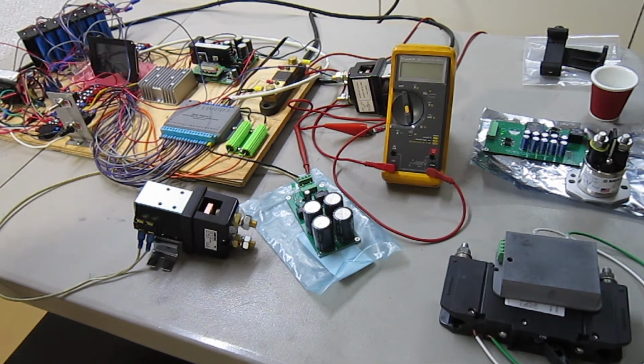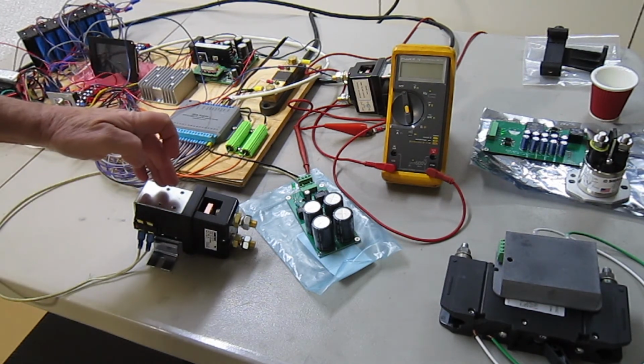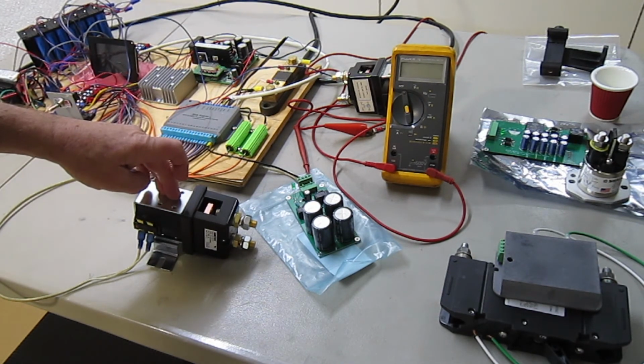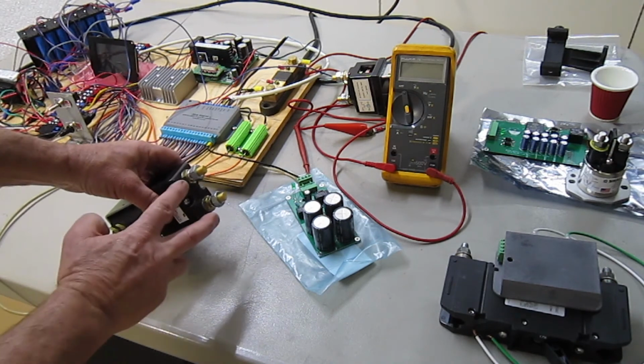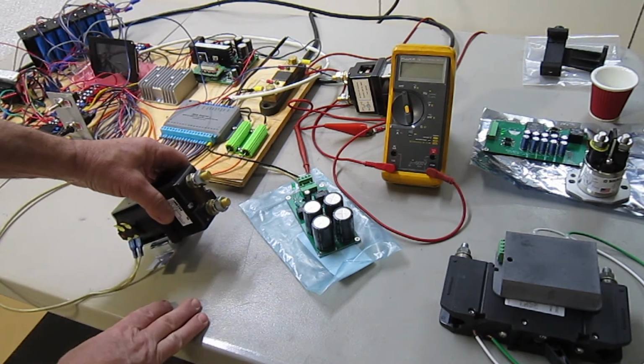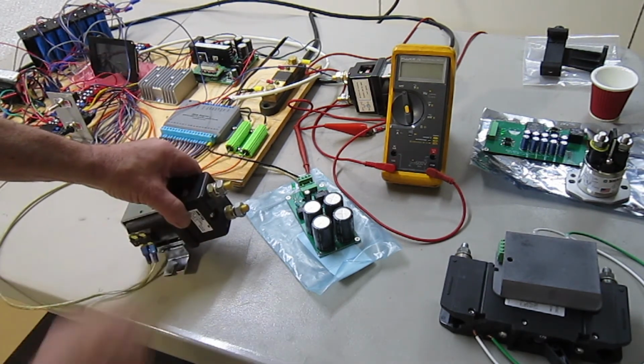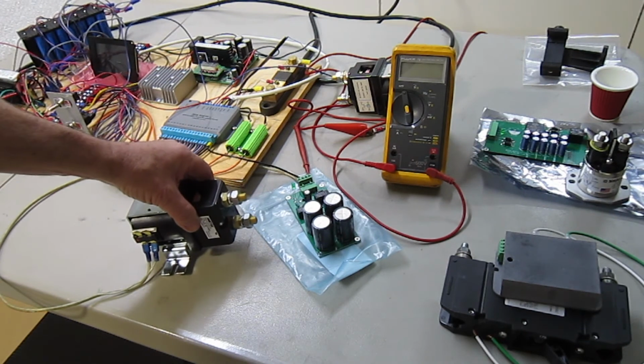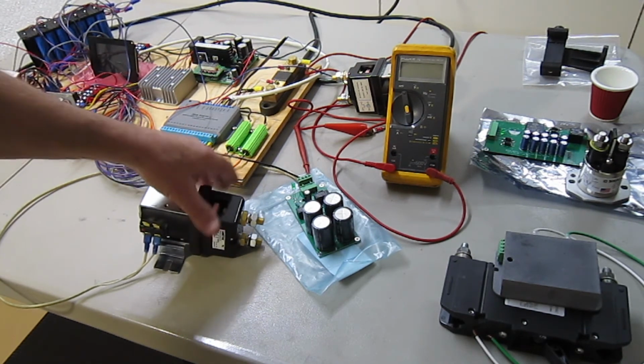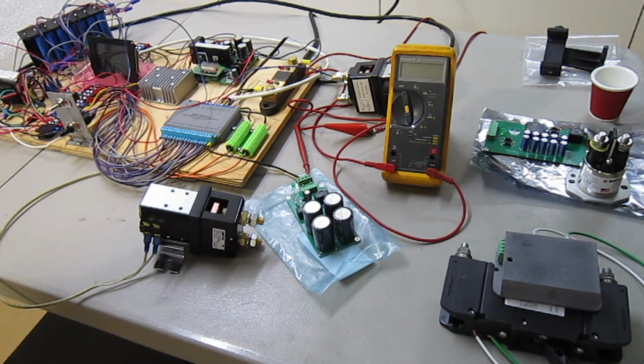Those latching contactors, a single coil design like this, have one version with just the studs, and then another version which I really like. It's got bus bars on it with 2 holes on each side, so you could actually connect 2 batteries together in parallel right on the contactor, and you wouldn't need a separate bus bar, so that would save you some money.